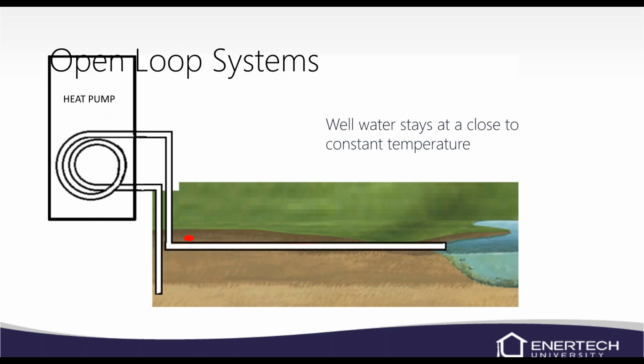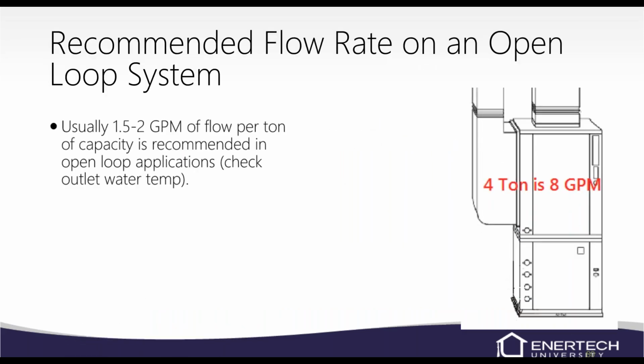That was pretty simple. Open loop. Well water stays at a constant temperature. We're not using antifreeze. Basically, this would be considered a pump and dump. Some guys don't like that term, but that's what we're doing. We're pumping from somewhere and dumping it somewhere else. Recommended flow rates, 1.5 to 2 GPM is recommended for open loops.